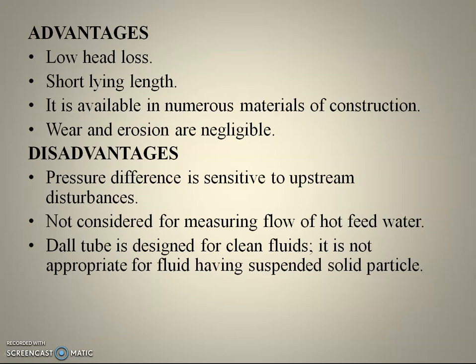The advantages of the Dall tube are: low head loss, short laying length, and it is available in numerous materials of construction — such as gun metal and cast iron. Short laying length means the Dall tube is shorter in length compared to the Venturi tube and orifice meter. Low head loss means the pressure loss is minimum in this Dall tube, as the differential pressure recovery is high.